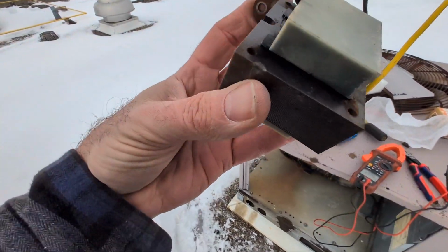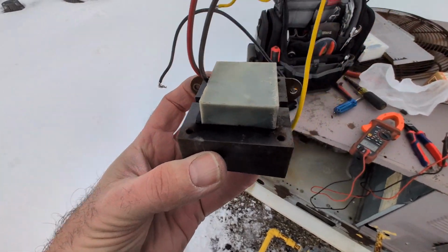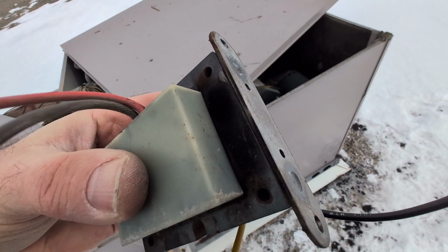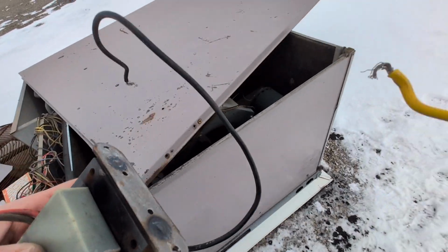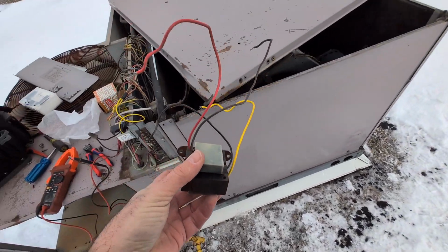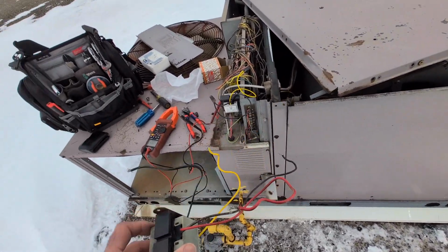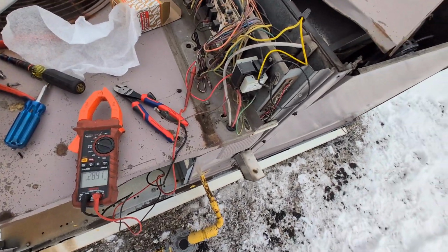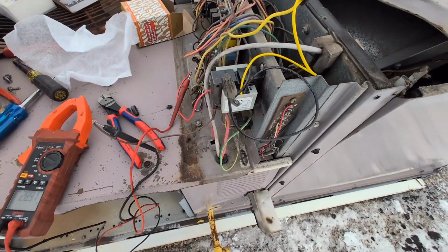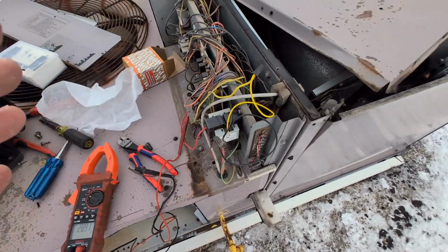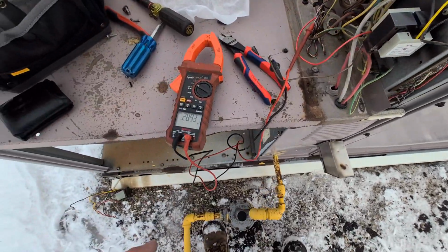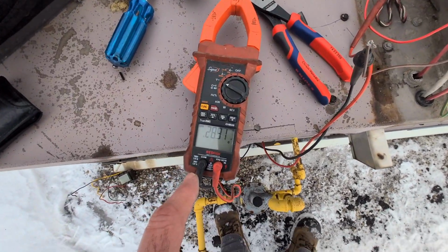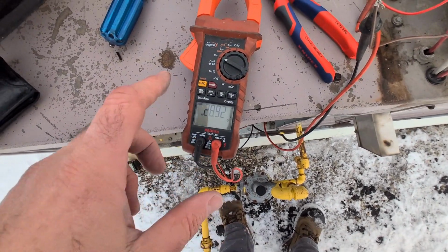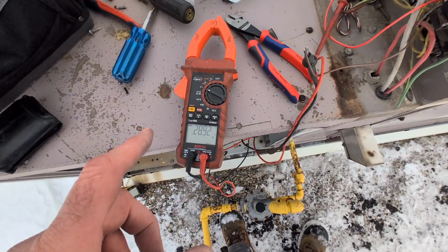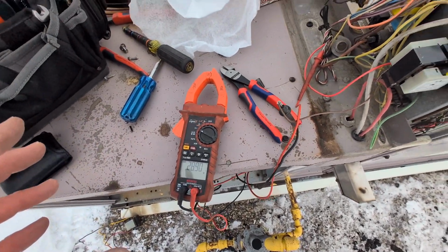I've got a control transformer. It's hard to see, but there's some burn marks on it, and I was not getting 24 volts out the other side of it. So what I've done is I've replaced the transformer. There's the new one on there, and I have not hooked up the 24 volt side yet, but I am checking voltage. So I have 28 volts coming out the other side of the transformer. So the transformer is working.